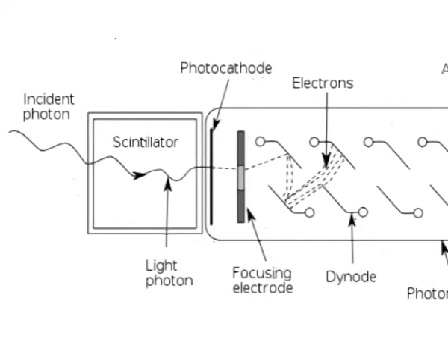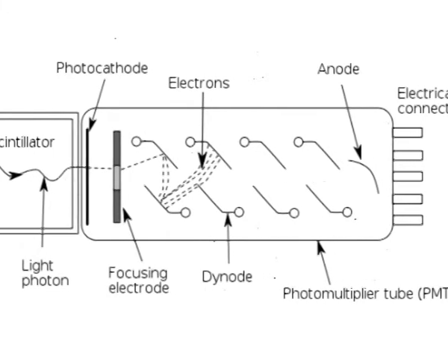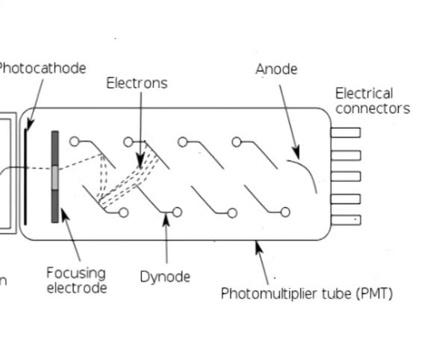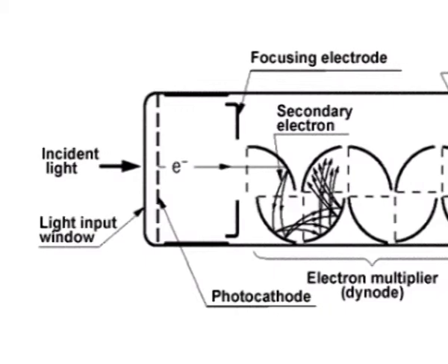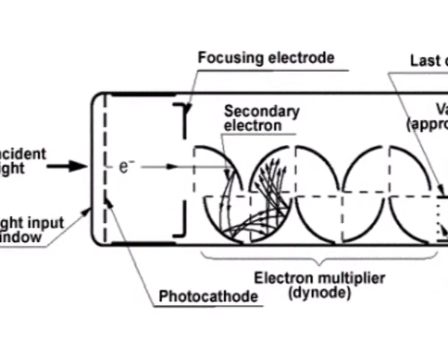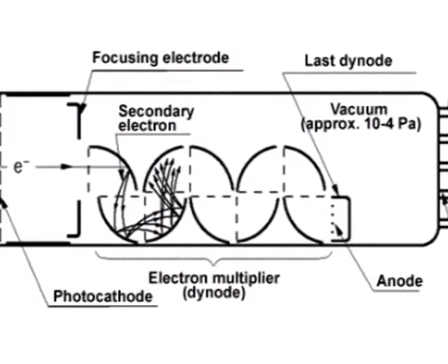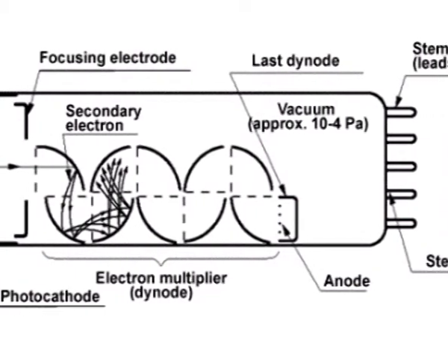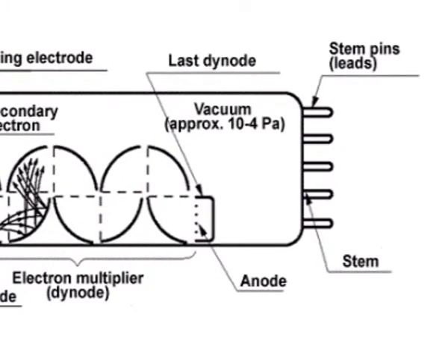It is the combination of photodiode and electron multiplier. It consists of evacuated tube, contains a photocathode, has 9 to 16 electrodes known as dynodes. These detectors multiply the current produced by incident light by as much as 100 million times, that is 160 dB, in multiple dynode stages, enabling, for example, individual photons to be detected when the incident flux of light is very low. Unlike most vacuum tubes, they are not obsolete.